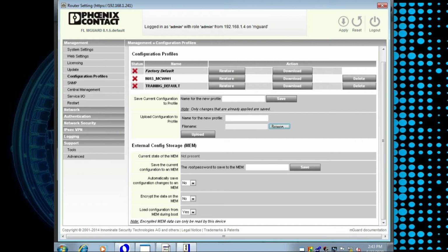So now let's talk about troubleshooting the connection between the customer's network and the internal devices of the machine. Let's say you populated the NAT table with the IP addresses that their IT department gave you, and there's still no communication between devices. So your first go-to, like we talked about, is going to the tools page and pinging from the router itself. Let's say you ping internally, that works just fine. Let's say you ping externally, and that works as well. So what is going on? More often than not, the router is not configured. In order to configure the router, we have to upload a configuration file. So let's talk about how to access that file and how to upload it.